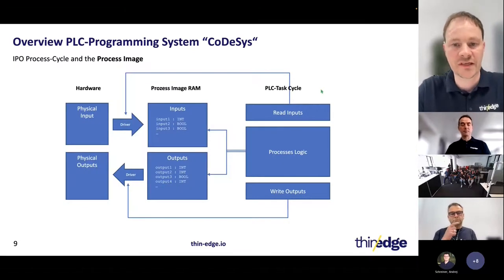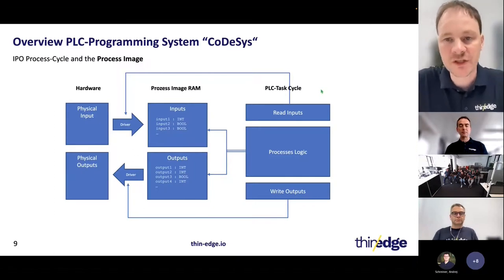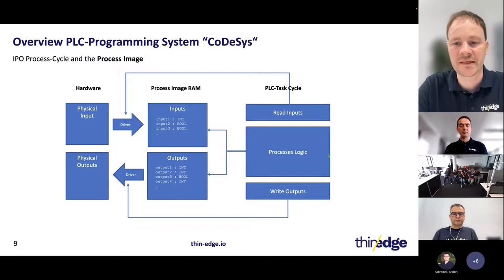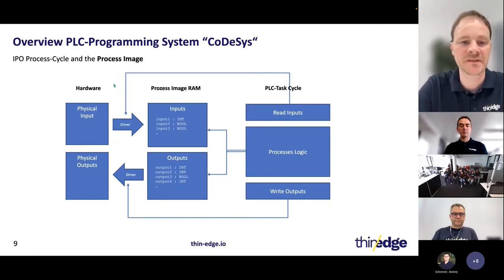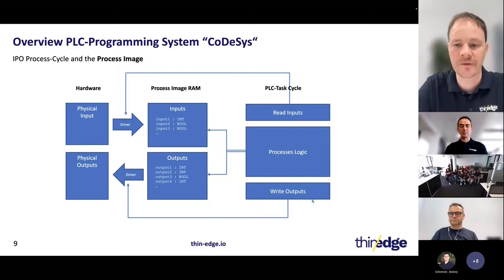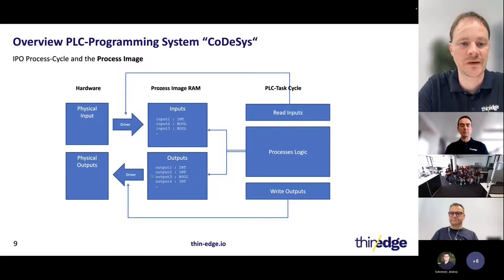Let's have a short look at the structure of a typical PLC application. The PLC application is executed in a cyclic task. On the left side of the figure you can see the physical hardware inputs and outputs, and on the right side the PLC application flow. In each PLC cycle, first a driver reads all physical inputs and stores them into RAM in the so-called process image. Next, the PLC logic is triggered and works on those inputs and the output area. After that, the outputs are written — drivers map all outputs from the process image in RAM to the physical outputs.